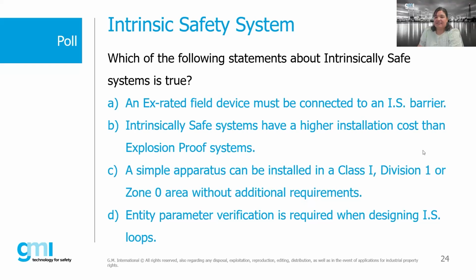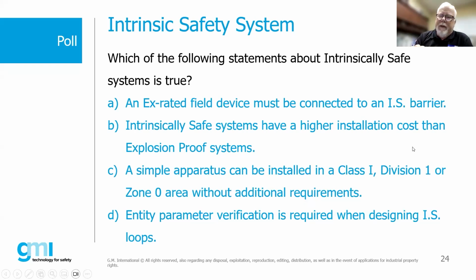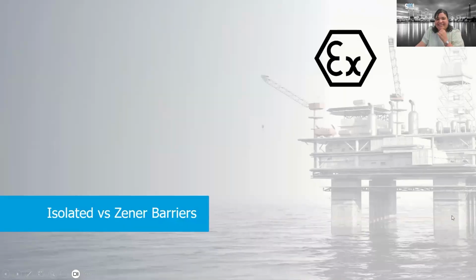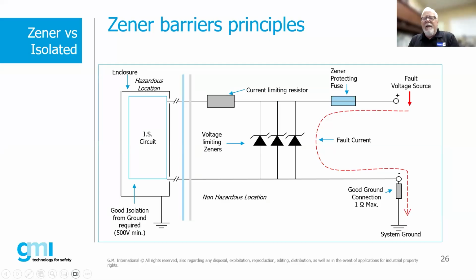And that simple apparatus can be installed in a class 1, div 1 or zone 0 area without additional requirements. It's somewhat true, but that doesn't mean that we can just take a simple apparatus and install it in that area. We do still have to do our validation. We have to do our DSD or control drawing to reference that simple apparatus. So yes, we can use it installed, but the additional requirements are to wire that up to an intrinsically safe barrier and then validate it by the use of a DSD. Yeah, true.